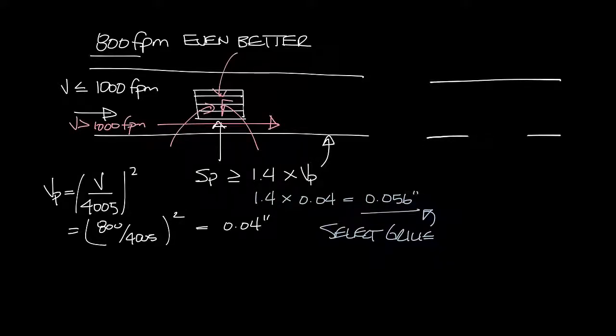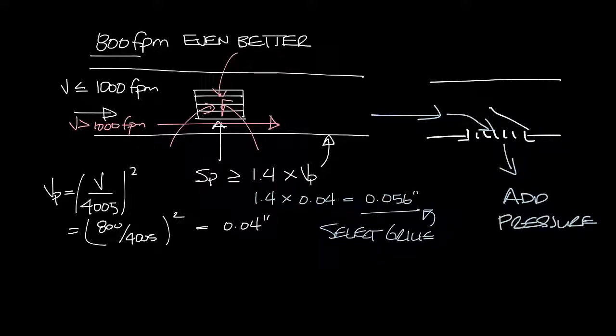So you can also use a scoop to help direct the airflow towards the grill, which would kind of look like this from the side, with the scoop going into the ductwork. And now that's going to direct the air out the grill, but you need to remember that this will add pressure loss in your ductwork and can increase the sound in your space. So there are your 2 rules of thumb for spiral duct mounted grilles.